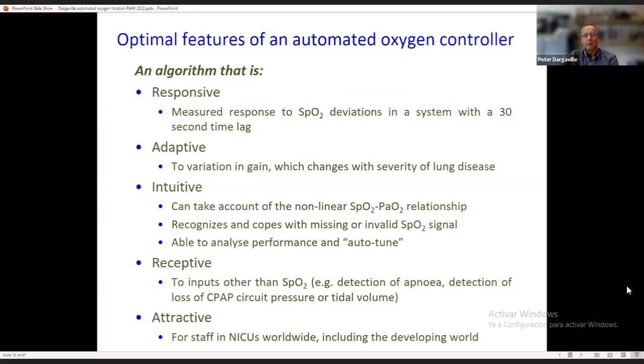It will continue to make changes by continuing to monitor the SpO2 inputs that are coming. And so it is possible to be continuing to make FiO2 adjustments even while you're waiting for prior ones to have their effect. The second thing that we could see that needed to happen with an algorithm is it needed to be able to be adaptive. And that means to the variation in gain, which is the step response in SpO2 that you would get for any given step response in FiO2.